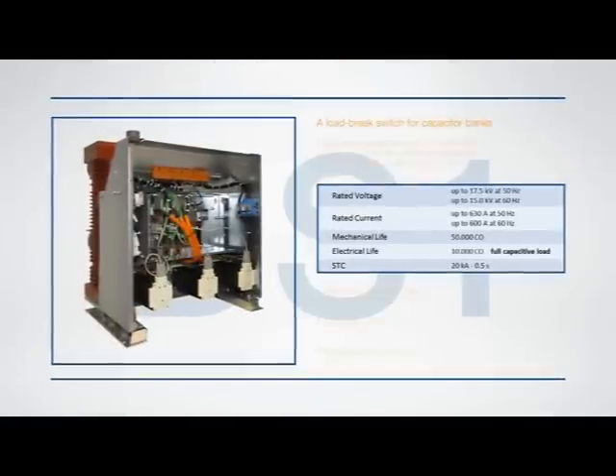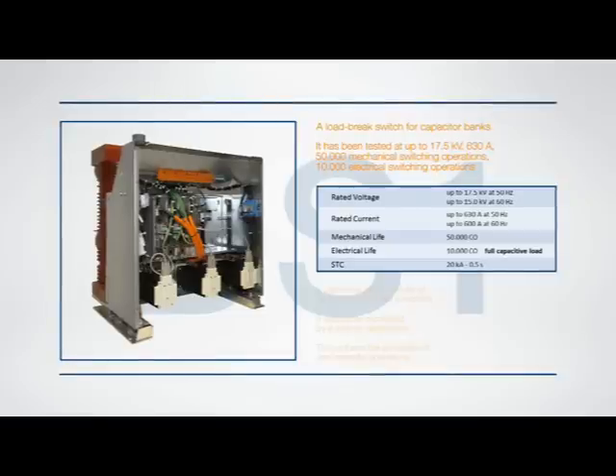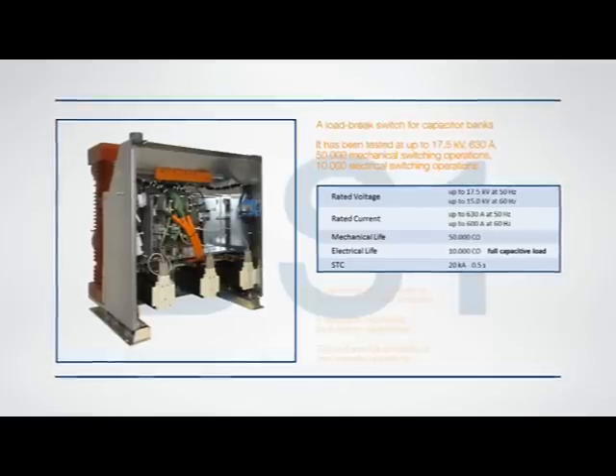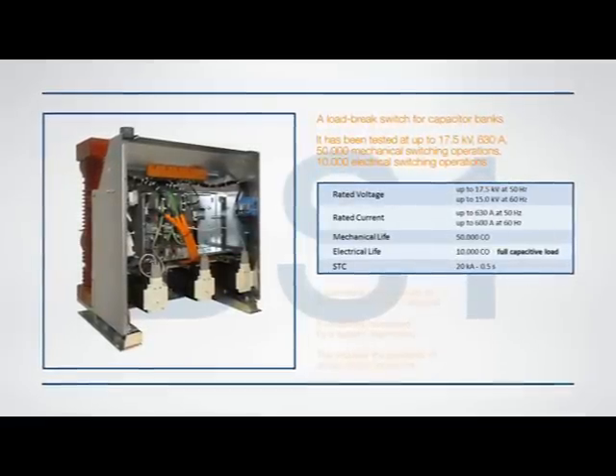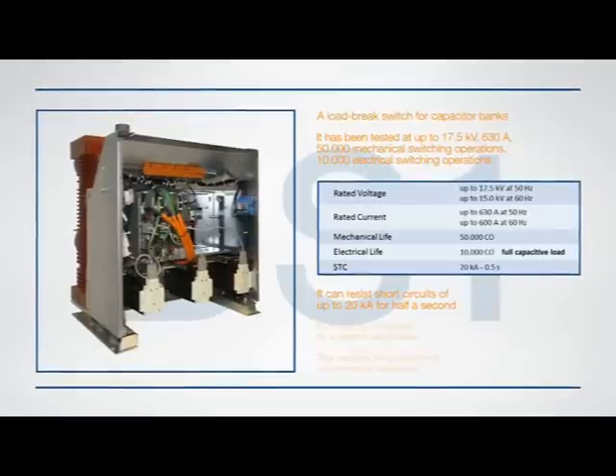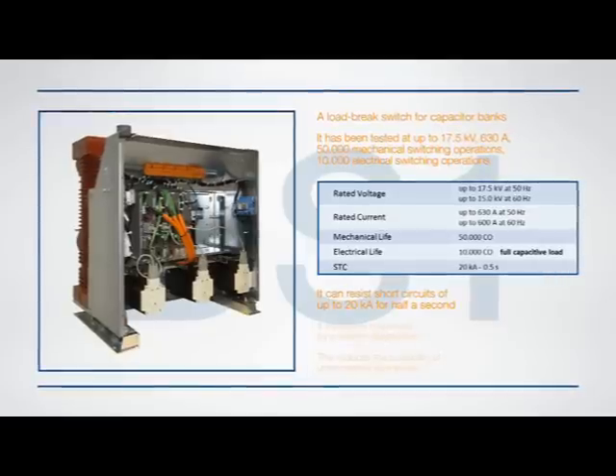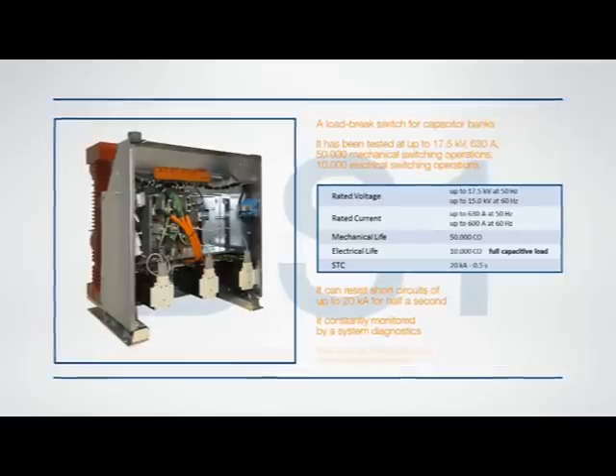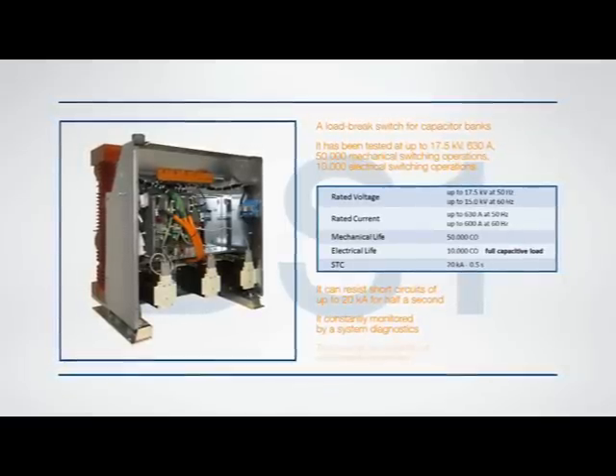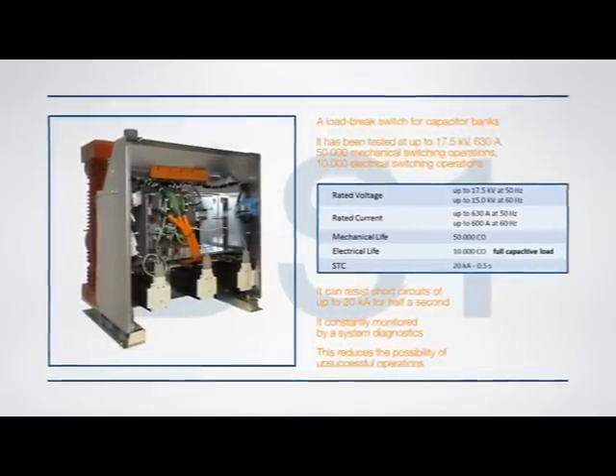The DS1 switch has been tested at up to 17.5 kilovolts, 630 amps, 50,000 mechanical switching operations, and 10,000 electrical switching operations at full capacitive load. It can withstand a short circuit current of up to 20 kiloamps for half a second, thus enabling the upstream protection device to isolate the fault and safeguard the power factor correction system. It is integrated with the system diagnostics, constantly monitoring DS1 status, which reduces the possibility of unsuccessful operations and consequently of unpredicted plant and network outages.